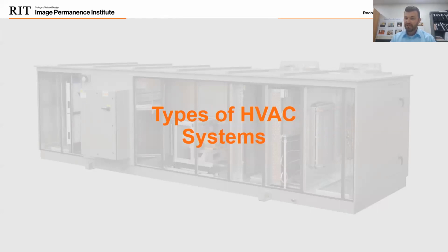First of all, would tighter deadbands result in more wear on the system as well? Question is, would tighter deadbands result in more wear on the system? It's going to be more energy. I can't say it's more wear on the system. It's going to definitely lead to more energy use. You're going to use more heating, more cooling to achieve those conditions. But I can't say for sure that would lead to more wear in the unit. Again, you're going to require more heating or cooling.